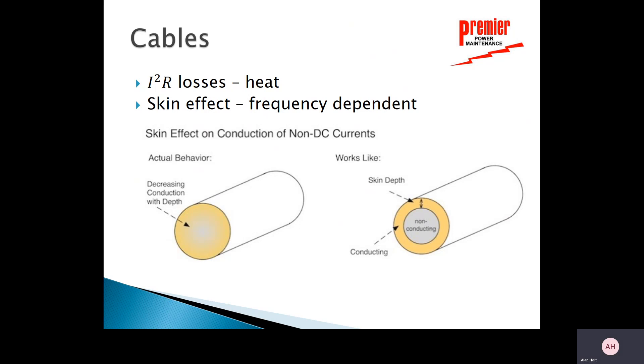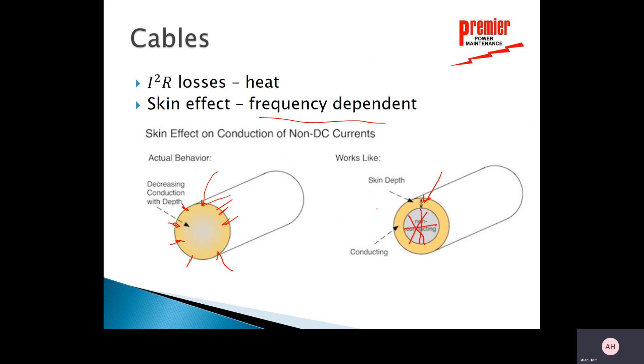On cables we have I²R losses — losses due to current flowing through copper or aluminum conductors. Current tends to flow on the outside of a conductor, which is why multi-conductor cables with several small conductors provide more surface area for current flow. This skin effect — the tendency to flow along the outside — is greatly increased by frequency. As frequency increases, current flows only near the outer surfaces of the cable, creating significant heat in the cable.